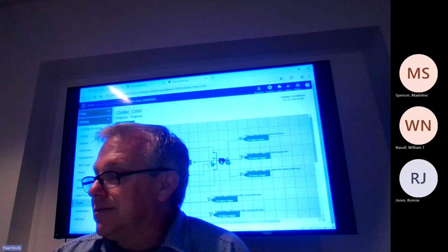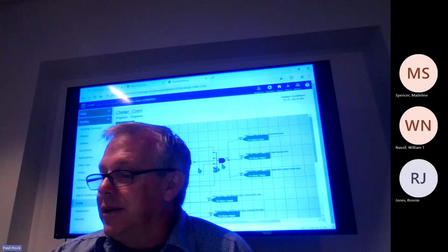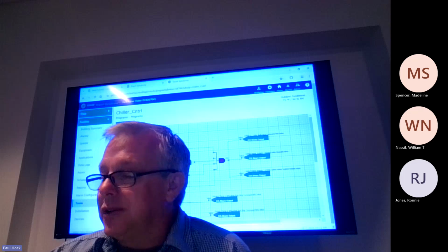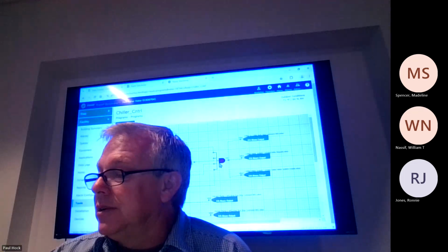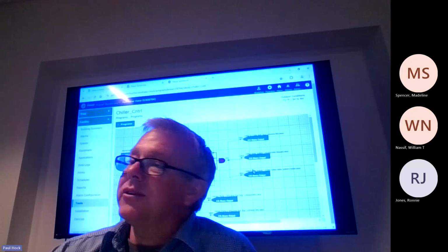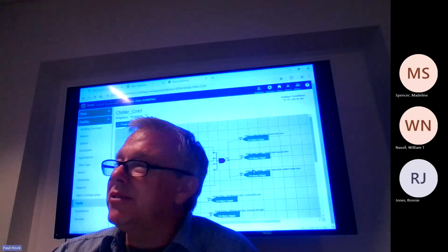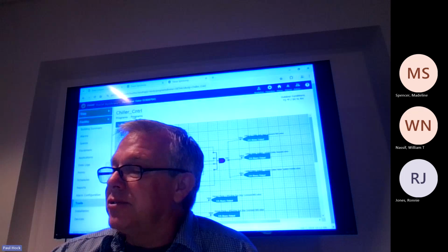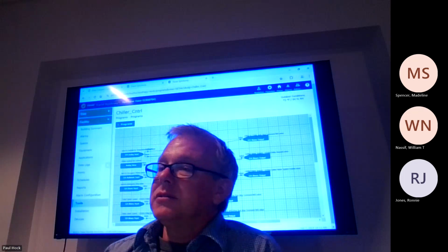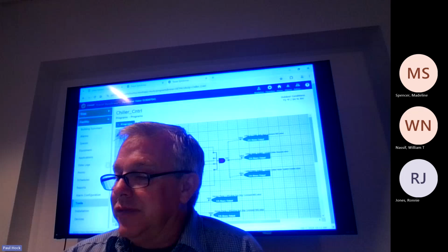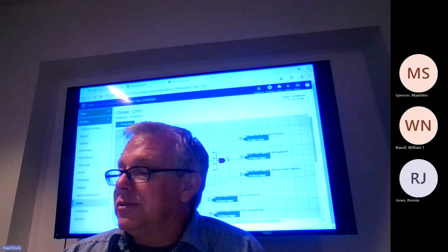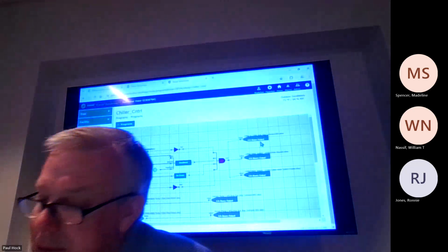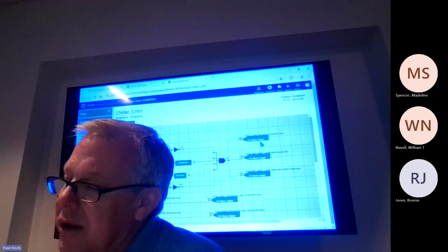That you can tell. You can go in here and say, okay, this is looking for all these variables right here. So if something was false, it would shut your chiller down. So you can get in the program and do a little bit of troubleshooting if you want. Then all I have to do is look and see what was false on this guy. My outside air temperature failed. That goes true. That's going to turn false. It's going to shut your chiller down. That's probably not a good idea.